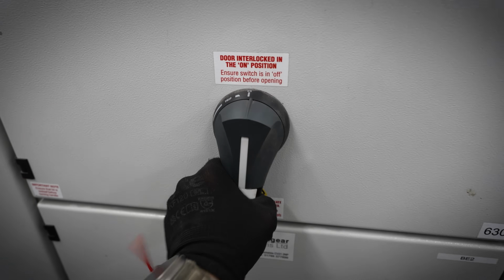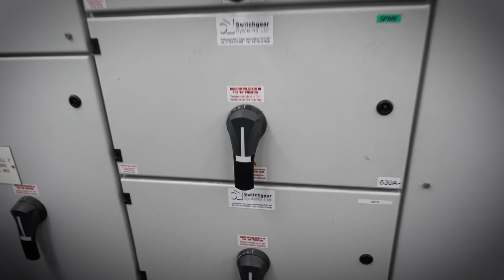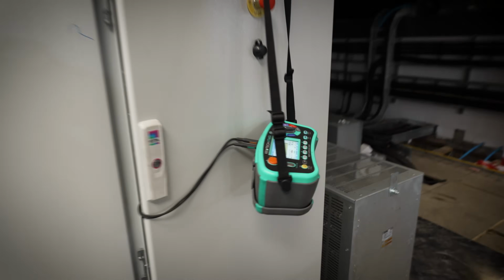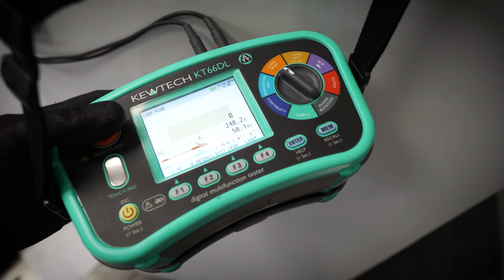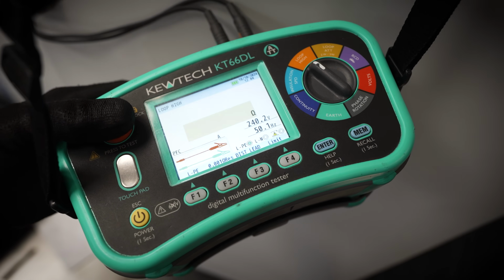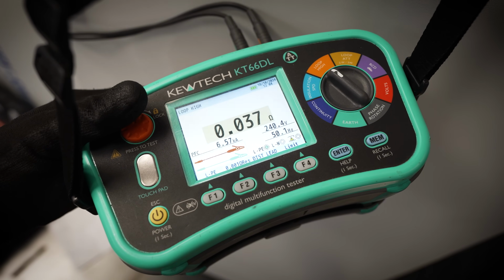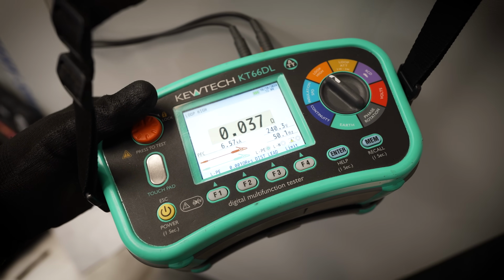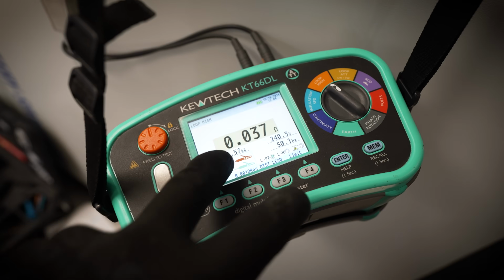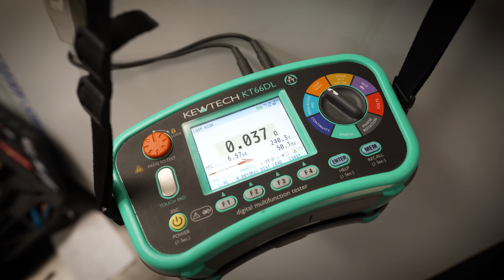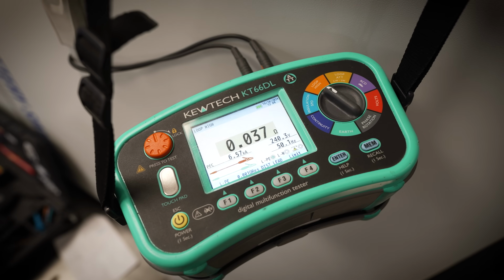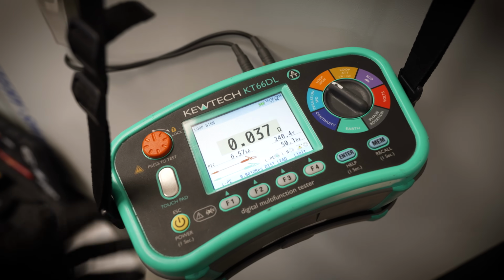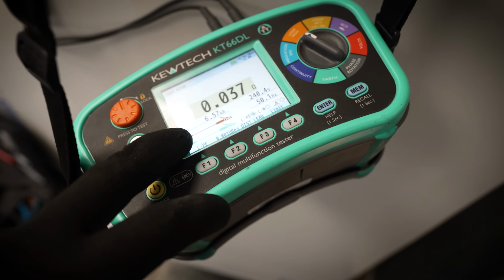Ready? We are on. Hopefully we've got 240. We have got 240. Let's press test. 0.037. Perfect. Literally as we designed it. That's insane. That is actually insane. Cool. Well, that's the first one. 0.037. Now we've got to go test L2 and L3.